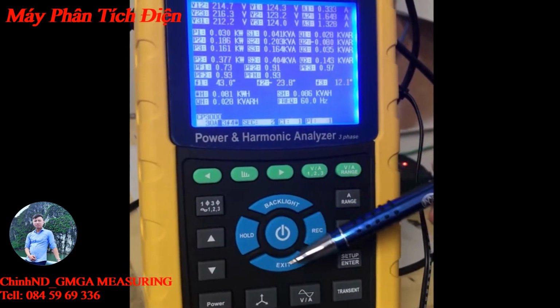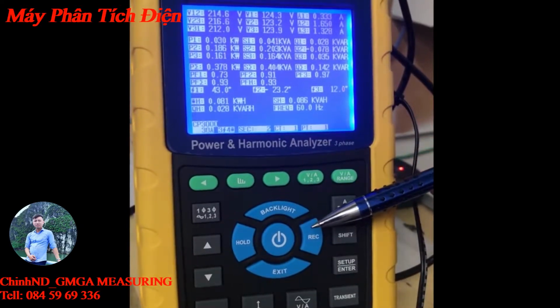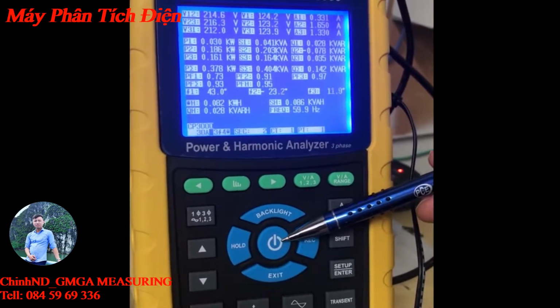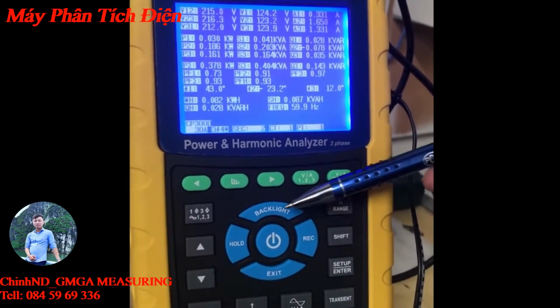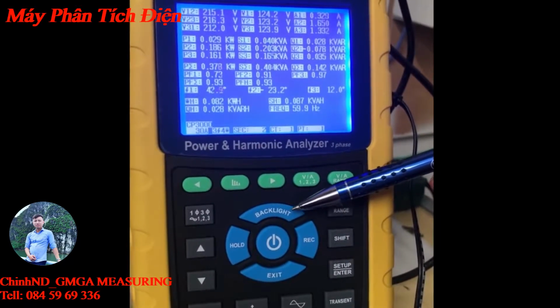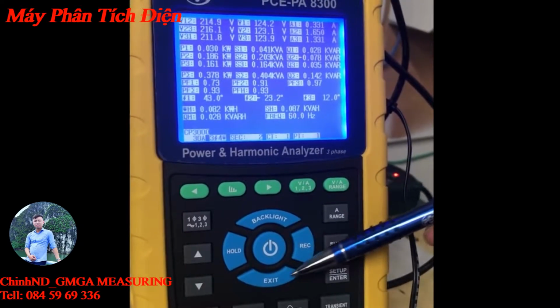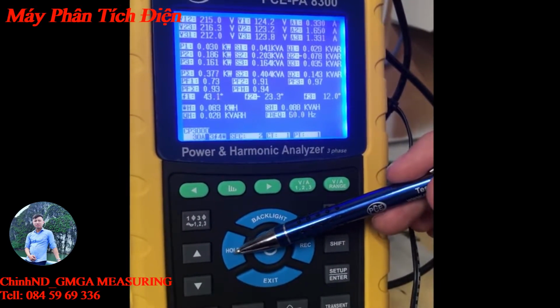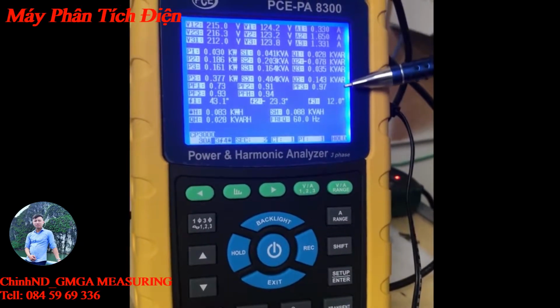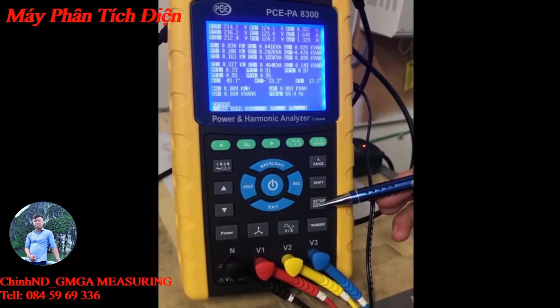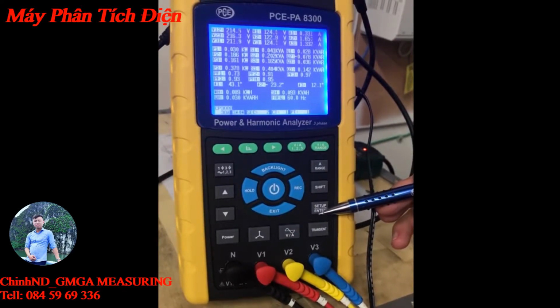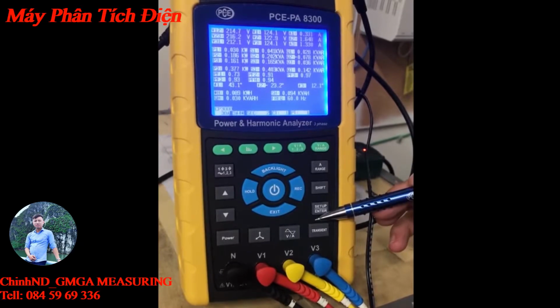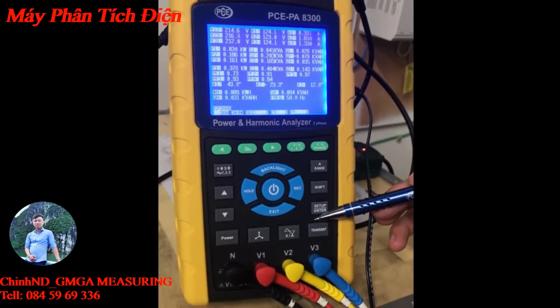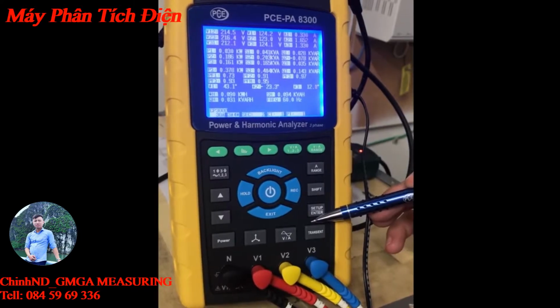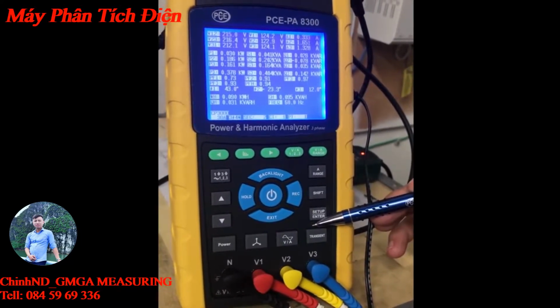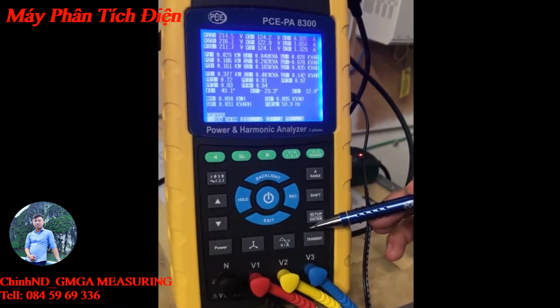These blue buttons here are basically your home buttons, pretty self-explanatory. This is your on-off button, it takes about 20 seconds to initialize. This button is for your backlighting. This is your record button, your exit button, and your hold button, which will freeze the data on the screen. This is your setup button, where you will be setting up the time and date, formatting the SD card, or deleting data. You can also set the sampling time, set the potential and current transformers, select the current clamp types, as well as the RS-232 output selection.